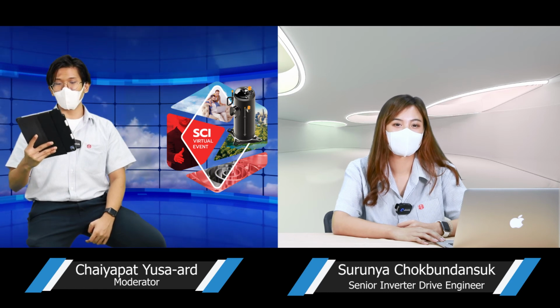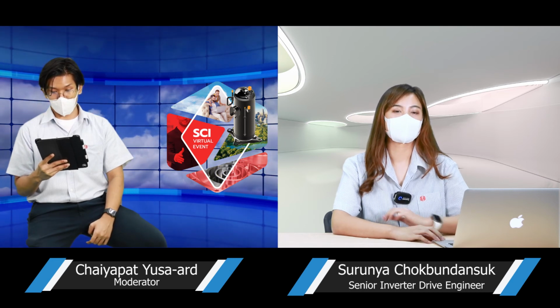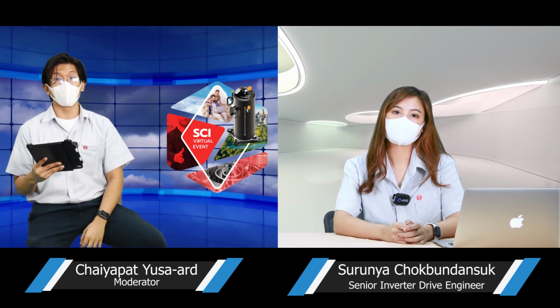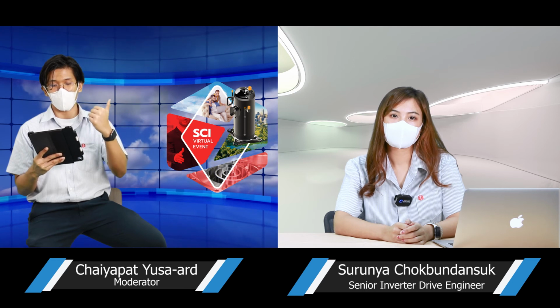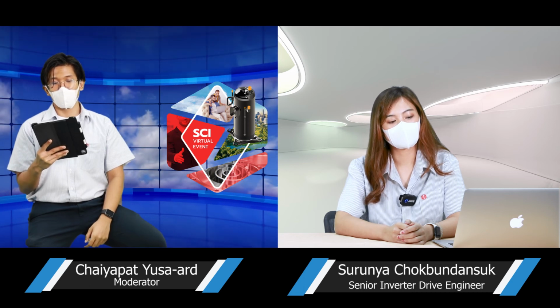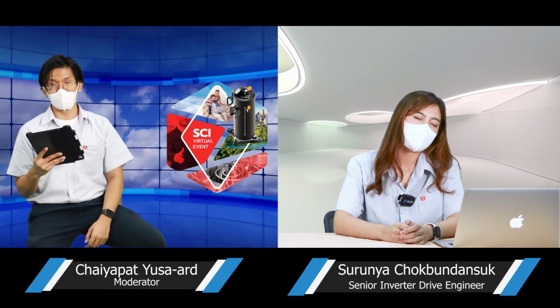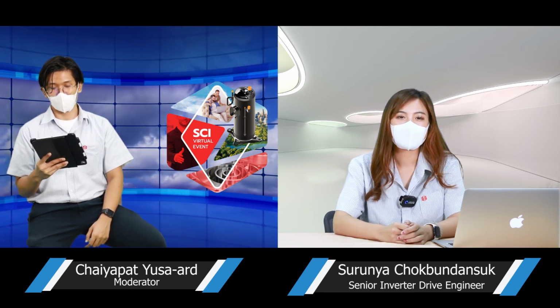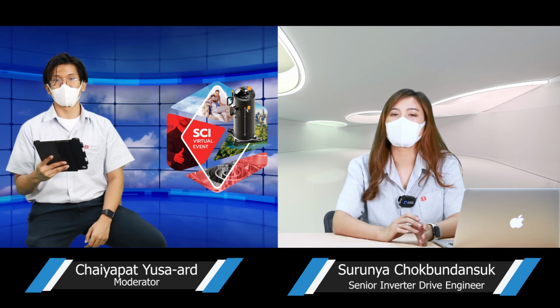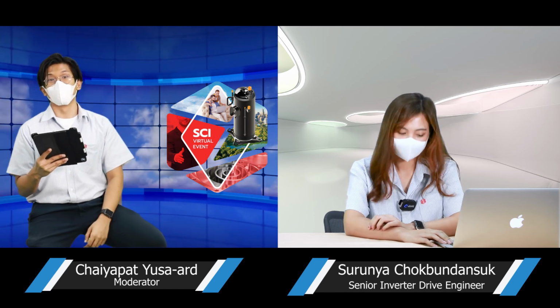All right, let's move on to the next question, and I think this one is very interesting. For the driver that comes with no enclosure, I mean for types E, G, and F, are they certified to use with flammable refrigerant? Yes, they are. Actually, the driver certification is certified at the electronic component level. The enclosure is not important. All right, so the enclosure is not really the issue, right?